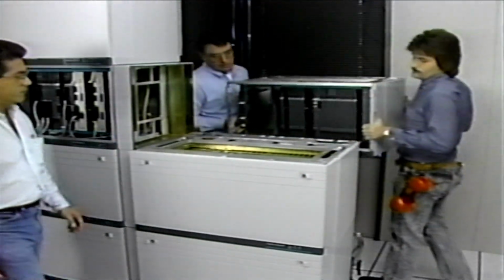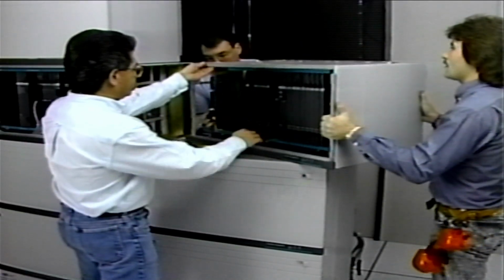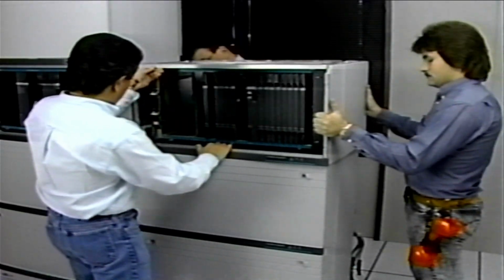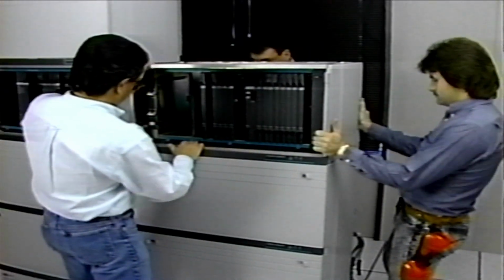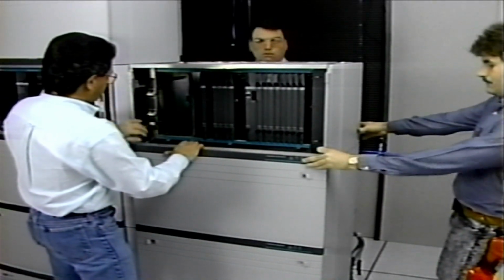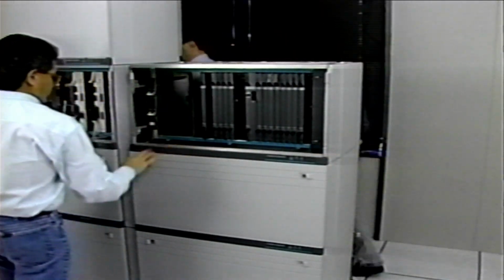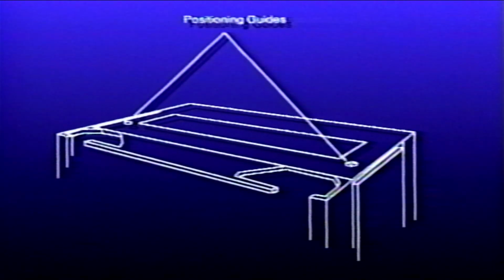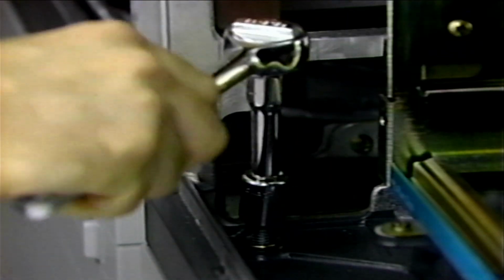If you have to add a module to the column, make sure the power supplies are removed before you begin. Additionally, you will need to have another person help you to safely position the module at the top of a column. Use the positioning guides to help you line up the module, and then insert the mounting bolts.